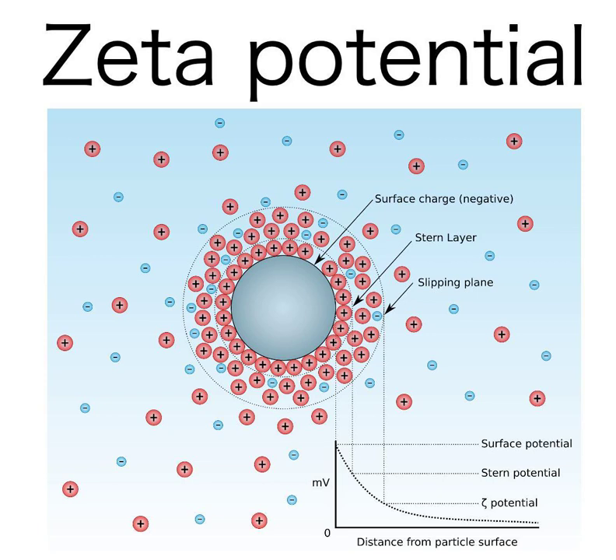Microelectrophoresis has the advantage of yielding an image of the moving particles. On the other hand, it is complicated by electroosmosis at the walls of the sample cell. Electrophoretic light scattering is based on dynamic light scattering. It allows measurement in an open cell, which eliminates the problem of electroosmotic flow except for the case of a capillary cell, and it can be used to characterize very small particles, but at the price of the lost ability to display images of moving particles. Tunable resistive pulse sensing (TRPS) is an impedance-based measurement technique that measures the zeta potential of individual particles based on the duration of the resistive pulse signal. The translocation duration of nanoparticles is measured as a function of voltage and applied pressure, from the inverse translocation time versus voltage-dependent electrophoretic mobility, and thus zeta potentials are calculated.